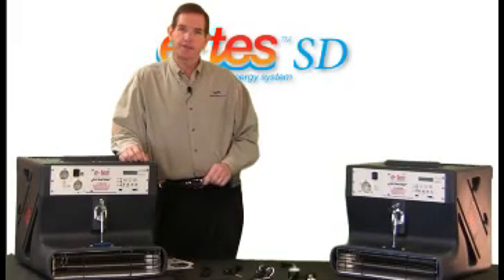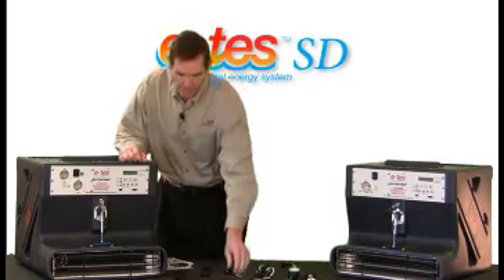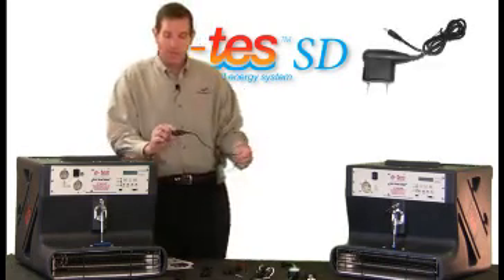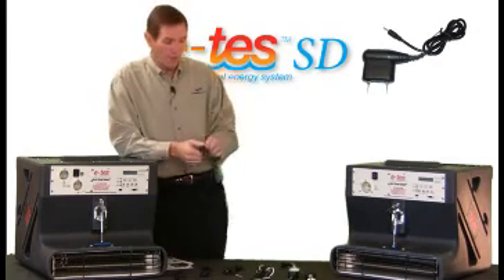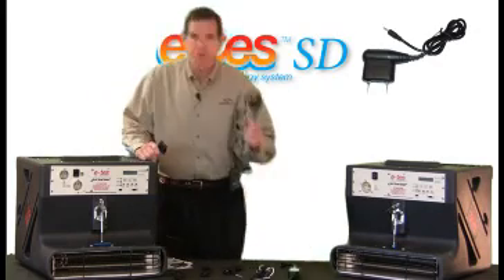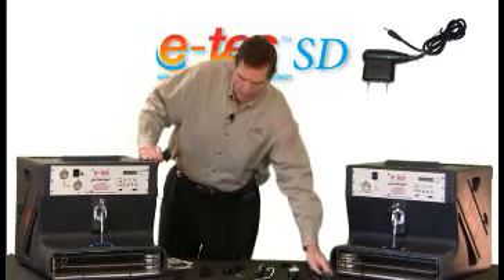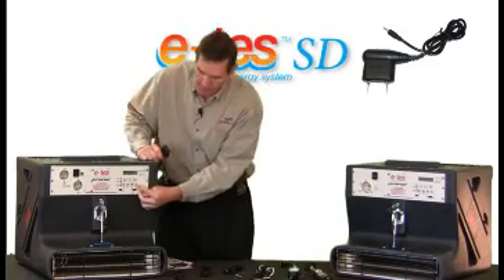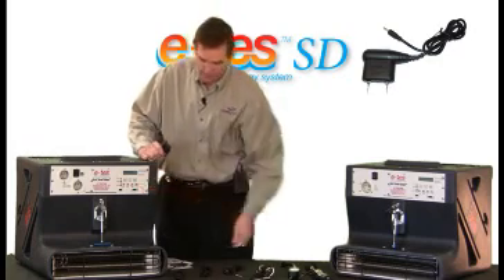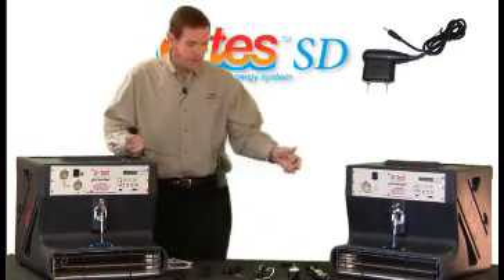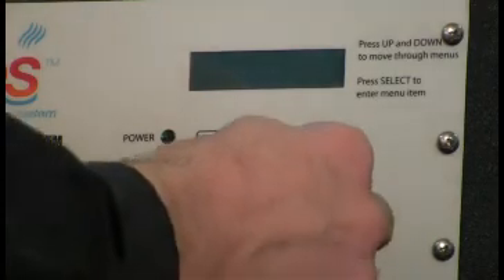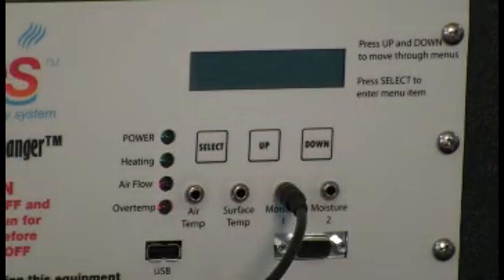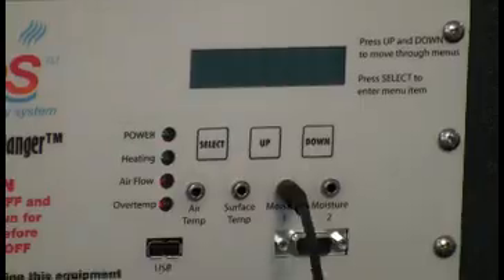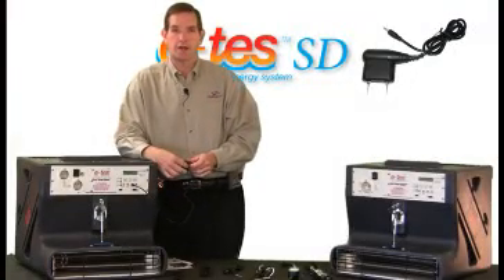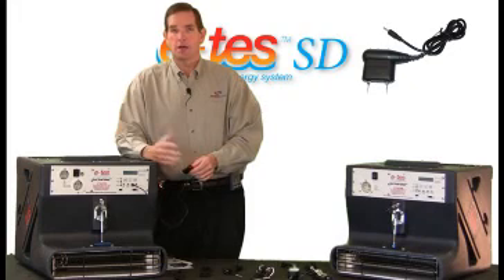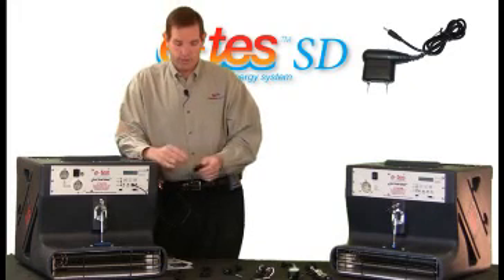The first feature I'd like to tell you about is the moisture content sensor. I have one here on the table. This is the typical small probe unit. We also have hammer probes that can be hooked into the unit. You'll be able to see here shortly we have two receptacles, a sensor 1 and a sensor 2. So what this allows you to do is plug the unit into one of the receptacles, and then with the probes inject them into the material, the porous material that you're trying to dry. Again, that might be hardwood, any type of substrate, I guess, for that matter.